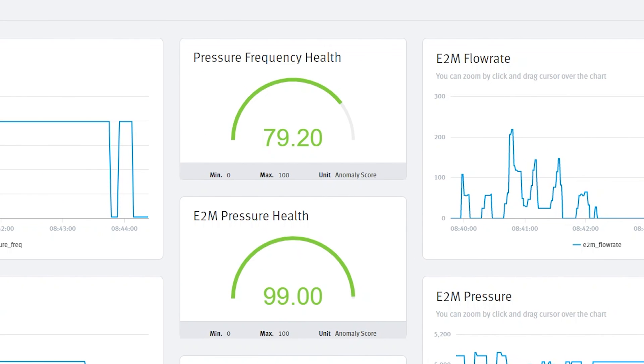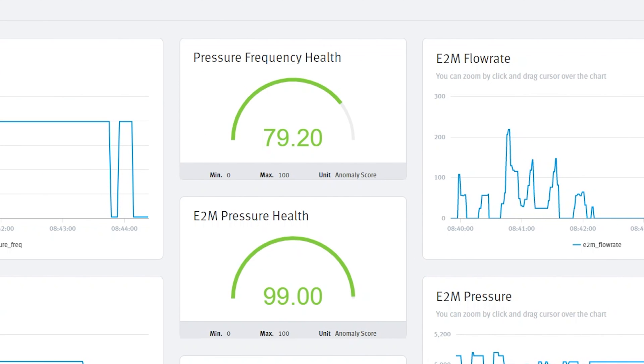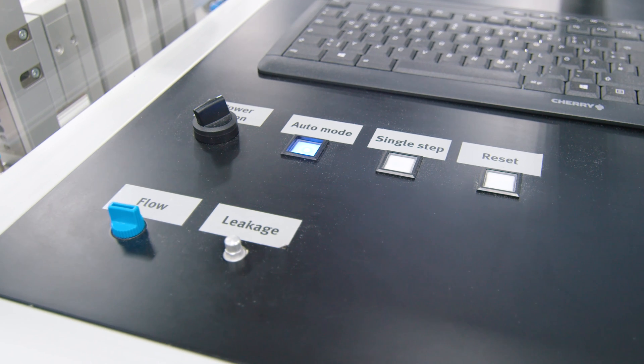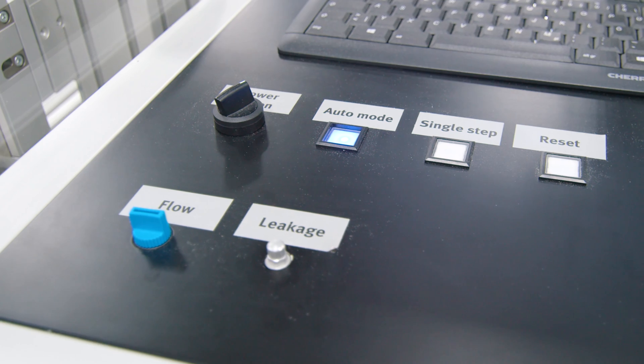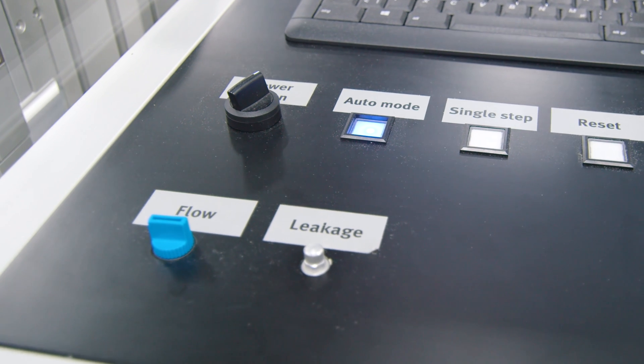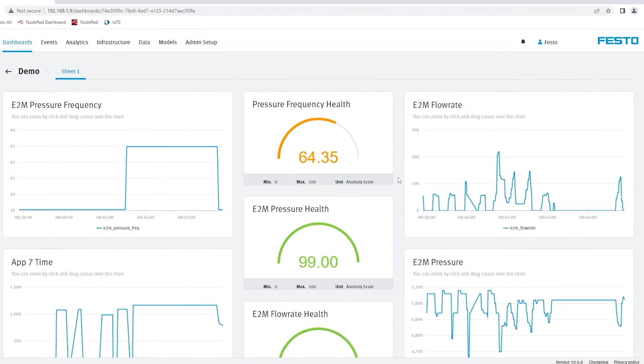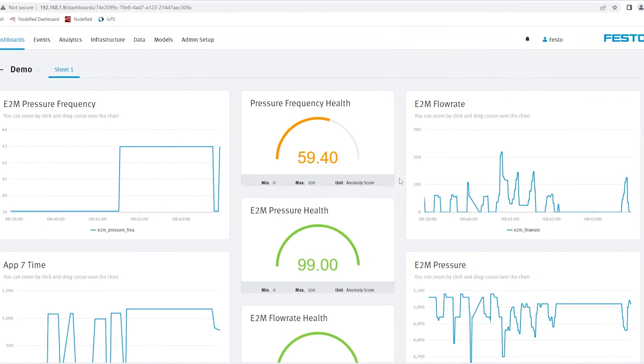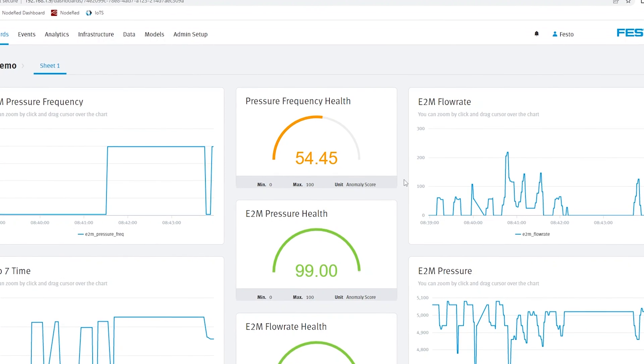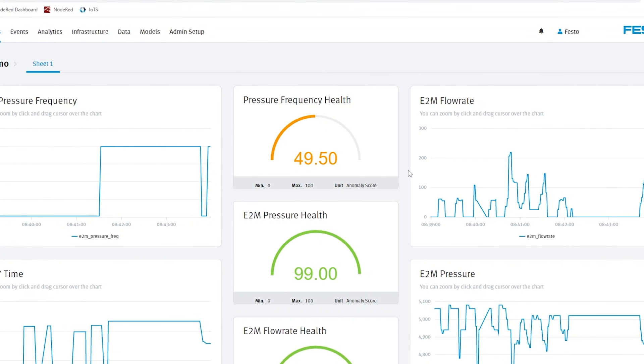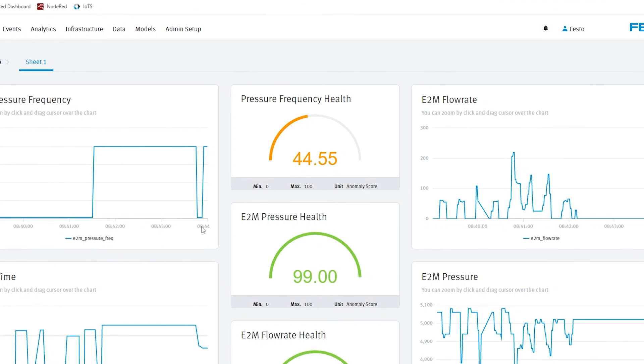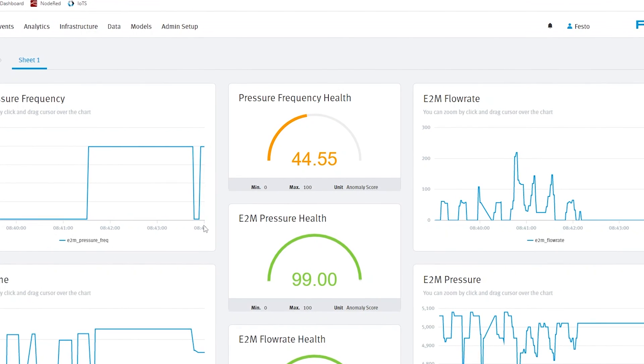To see a dramatic increase in that, there is a flow valve here that I could create a leakage. As I create a leakage here, you can barely hear it, but you see already that the pressure health is starting to decline, and the flow rate health.